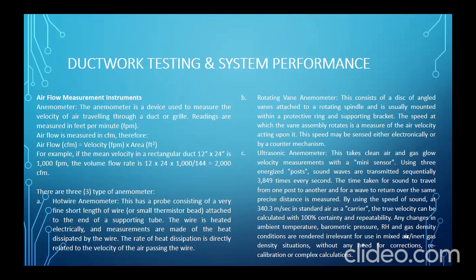B is the rotating vane anemometer. So, ito yung nabibili sa, meron to sa, tama, ito yata yun. So, this consists of a disc of angled vanes attached to a rotating spindle. It is usually mounted with a protective ring and supporting bracket. The speed at which the vane assembly rotates is a measure of the air velocity acting upon it. This speed may be sensed either electronically or by a mechanical mechanism. Diba? Bibili nyo. C. Ultrasonic anemometer.